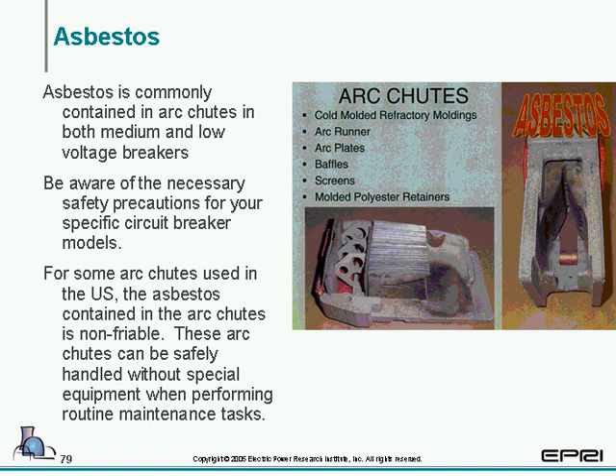We've had a lot of questions through the years about asbestos. Asbestos is commonly contained in arc chutes. This is the air magnetic breakers, in both medium and low voltage breakers. You should be aware of the necessary safety precautions for your specific circuit breaker models. However, some plants have done their own testing because they've had a safety concern, and for some arc chutes used in the U.S., the asbestos contained in the arc chutes is non-friable, and these arc chutes can be safely handled without special equipment when performing routine PM tasks.